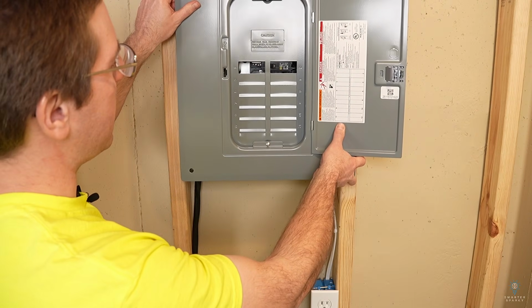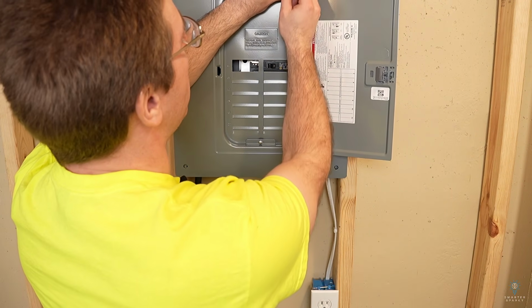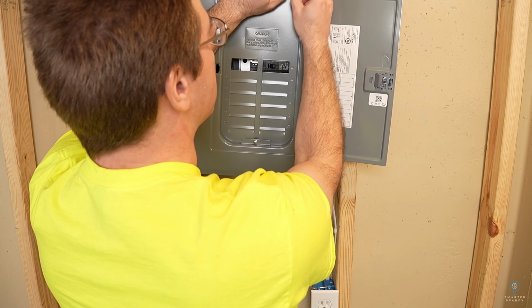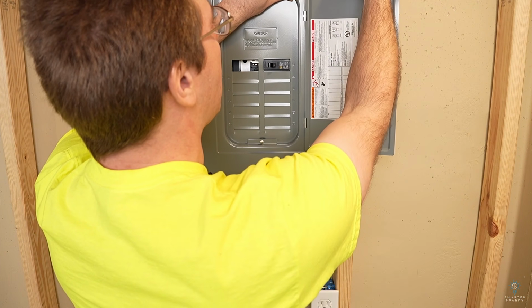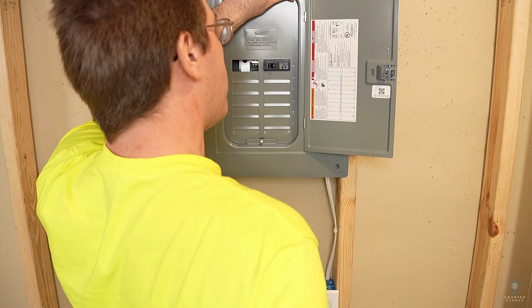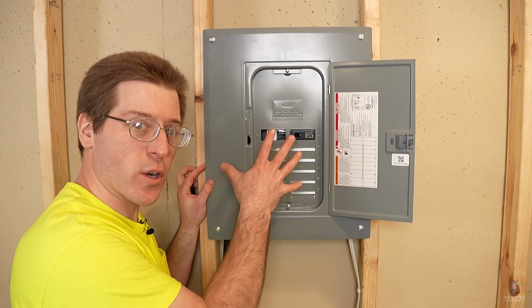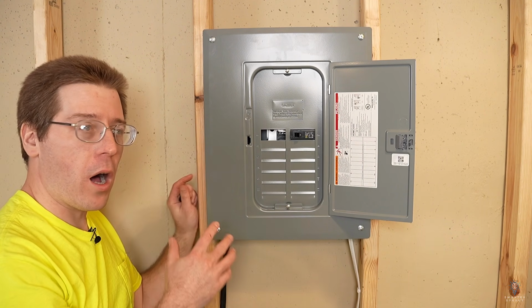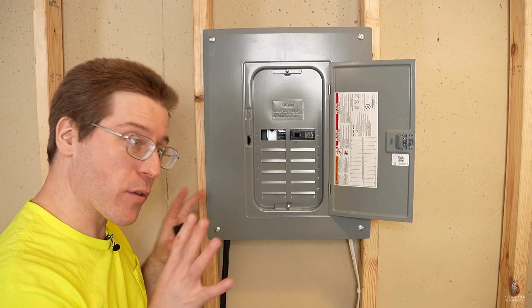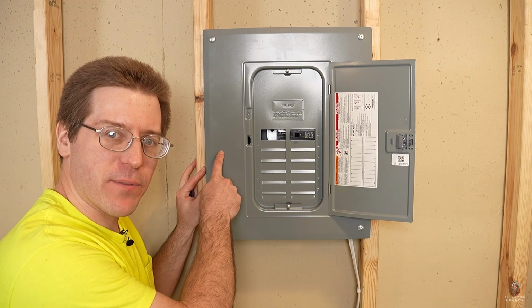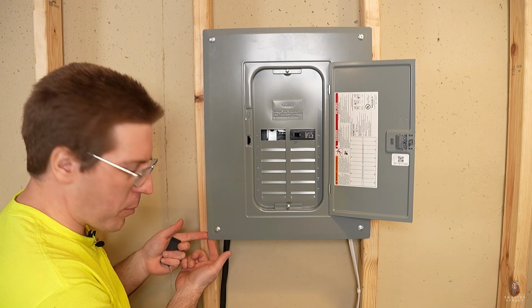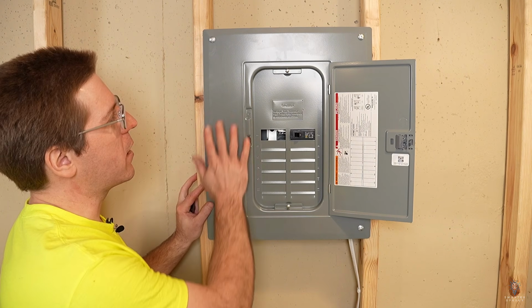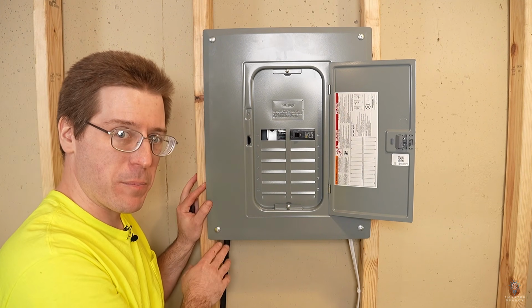So we can pop this on, and this is a flush mount cover. So this cover is actually specifically for installing inside of a wall. If you were installing this panel surface mount on like a concrete wall or on sheetrock rather than in sheetrock, you would need a different cover. Otherwise, there's these little sharp edges that hang over the edge. You want a cover that actually sits flush with the panel itself.